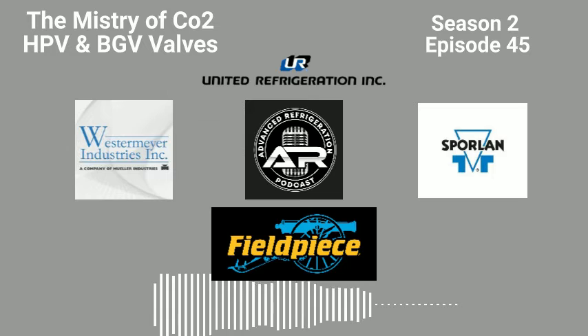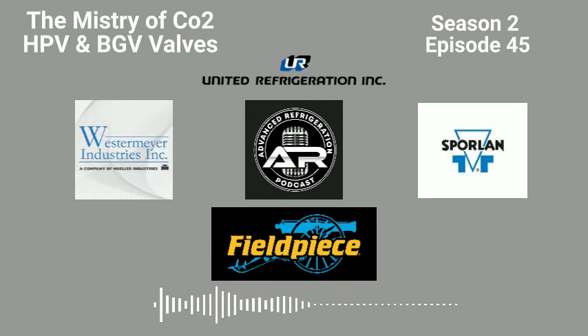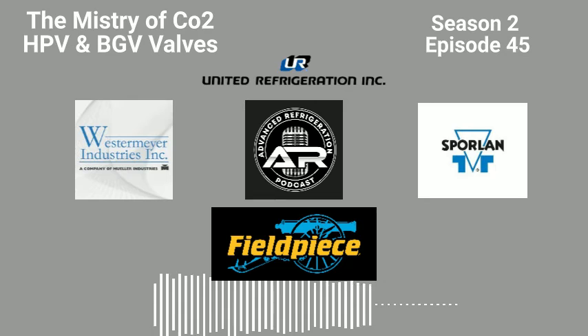You could tell it, okay, I'm calling for you to be 100% open. It also has a feedback signal of where the actual magnetic valve is. So it could say the feedback's only at 30%, but you're commanding it 100. Well, it may be because you're limited on the valve position, or it may be that your valve is stuck. And then you could see that. I like that part of that driver a lot more.